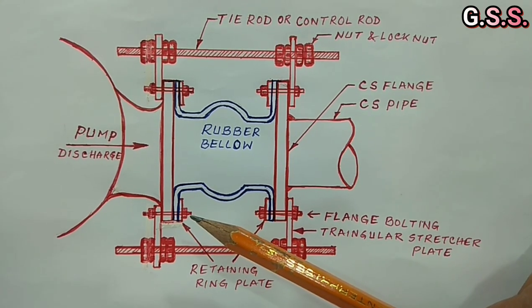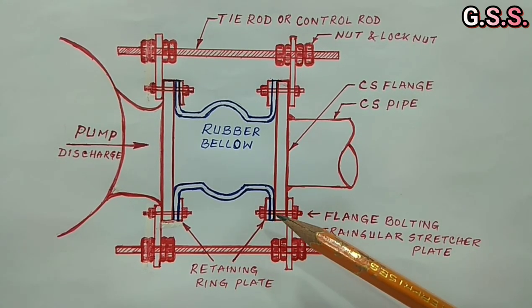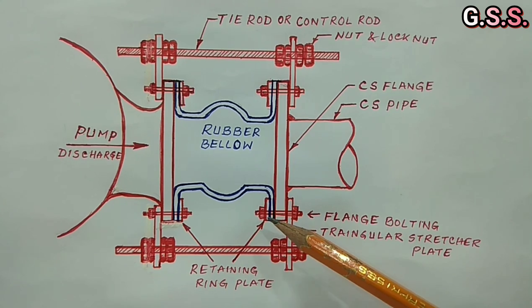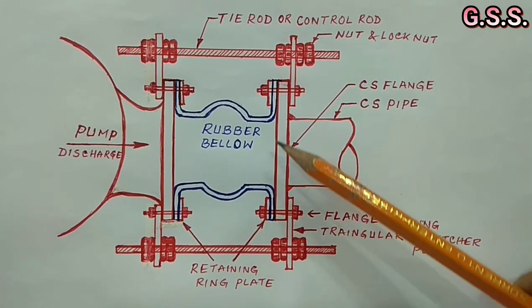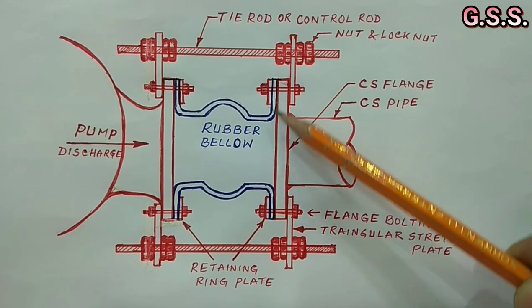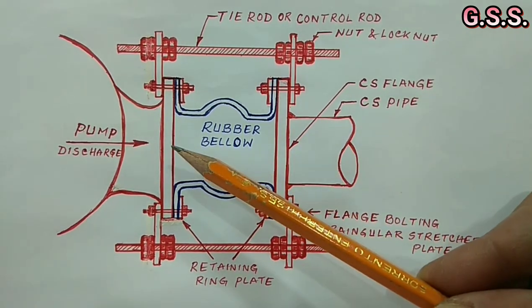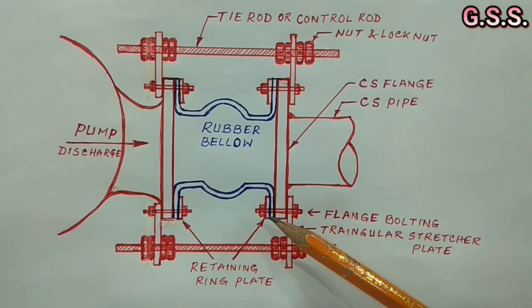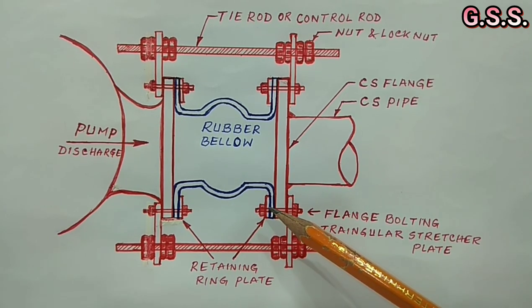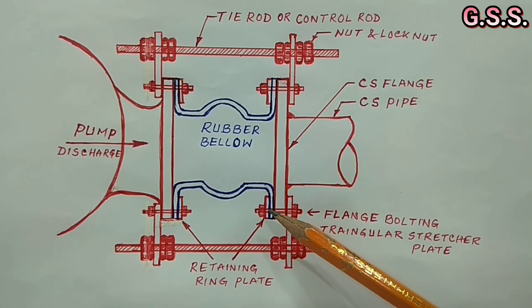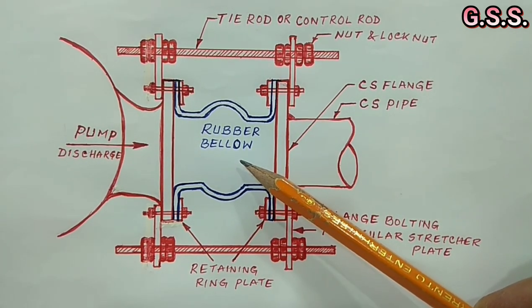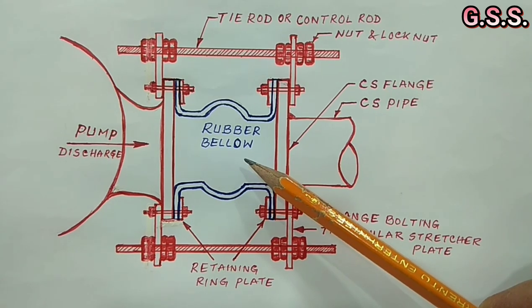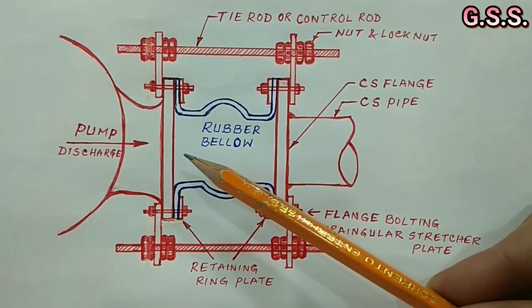Then pipe flange side bolts are tightened with curved retaining ring plates. There are four curved retaining ring plates on each side of the bellow having bolt holes at flange bolt circle diameter. So, after installation of the bellow in this way, bellow takes care of piping misalignments and makes pump nozzle as load free.